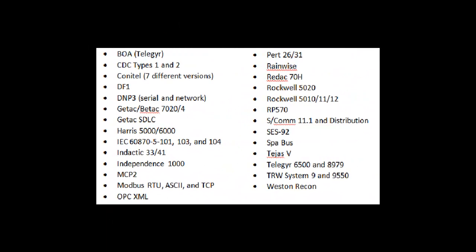As a protocol translator, the SPT software is supported in a Windows configuration management tool and a browser-like data viewer and diagnostic tool. The configuration tool, the SPT editor, is used to assign a protocol and a direction, master or slave, to each serial communication channel, with each channel getting its own designation. In theory, a 16-channel unit could operate with 16 different protocols.